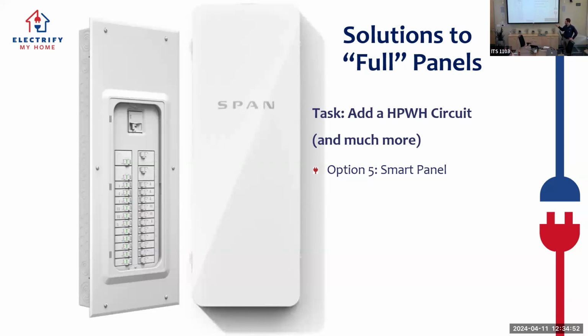The great thing about this is you can keep your 100 amp service and tell the span panel, I don't want my panel to ever exceed 100 amps, so make sure that never happens. And if it does, if we're creeping up, turn off this circuit first, this one second, this one third, and this one fourth. It can also operate as a critical loads panel for a battery, so when the power goes out, you can say I want to keep this circuit on but not the others. Really cool piece of technology, also really expensive, but it solves a really important issue.